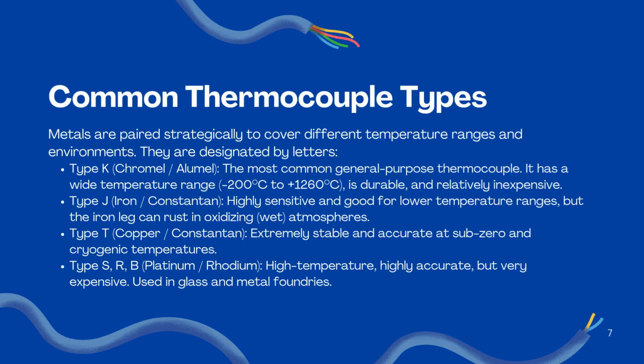So there are multiple types of thermocouples, and the metals are paired strategically to cover different temperature ranges and environments. They are designated by letters. For example, type K, which is chromel and alumel, is the most common general purpose thermocouple. It has a wide temperature range between negative 200 degrees Celsius and 1260 degrees Celsius. It is very durable and relatively inexpensive. Another one is type J, which is iron and constantan, highly sensitive and good for low temperature ranges, but the iron leg can rust in oxidizing wet atmospheres.